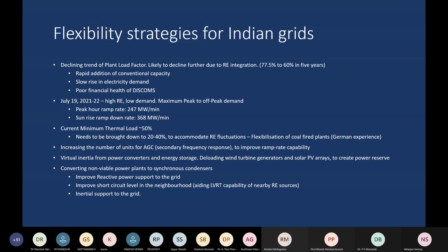Similarly, in the morning, when the sun rises, all the solar farms are expected to ramp up automatically. As a result, the thermal plants are expected to ramp down. So the sunrise ramp down rate on July 19th is expected to be 368 megawatts per minute. And the reason why this is so high is because the demand is very low on July 19th. This is not summer, it is not winter, it is monsoon. So nobody has switched on their air conditioners and nobody has switched on their heaters.